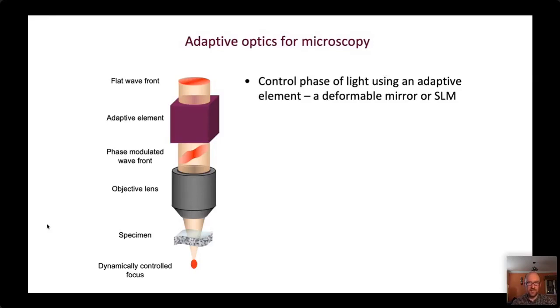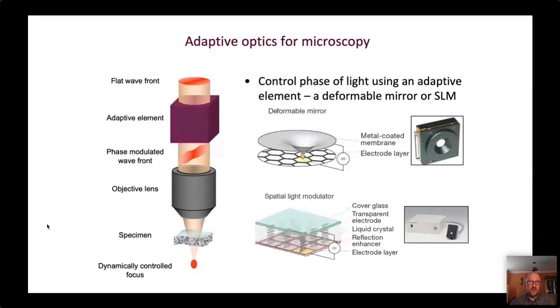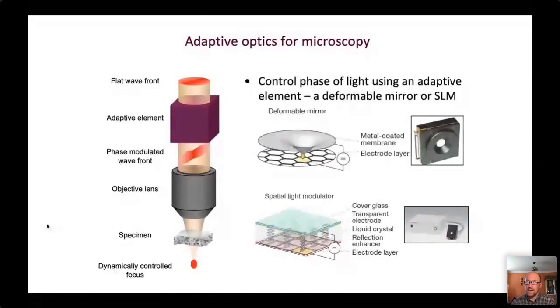The elements we use are either deformable mirrors — a reflective membrane whose shape we can change by applying forces with an actuator structure built into the mirror — or liquid crystal spatial light modulators, which change the phase of light by altering the properties of liquid crystal materials above each pixel. A deformable mirror is particularly useful in fluorescence microscopy with broadband and unpolarised light, while spatial light modulators are best suited to laser illumination with narrowband and polarised light.